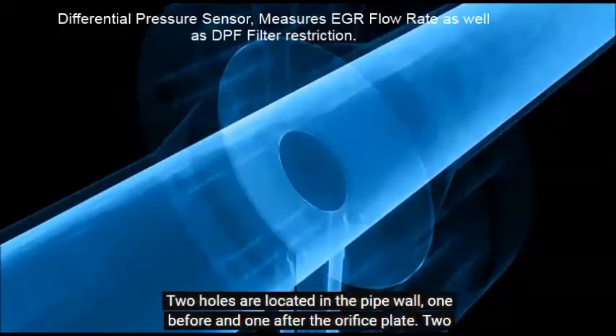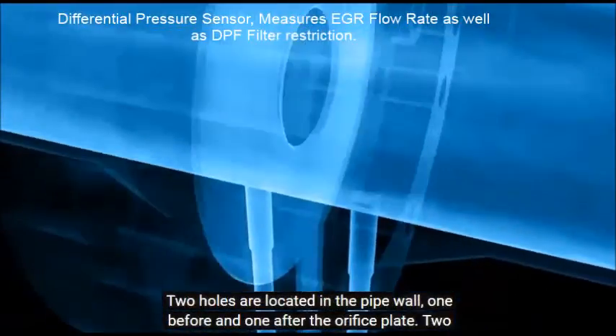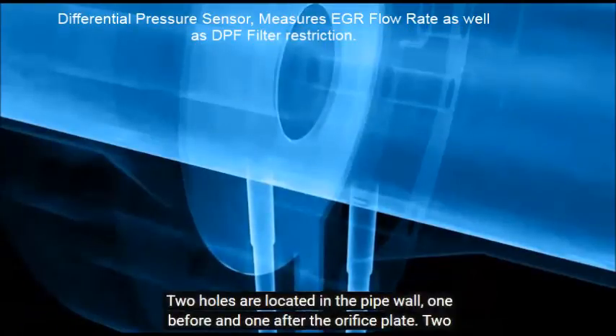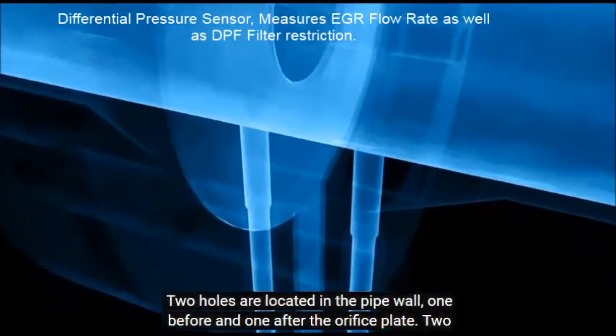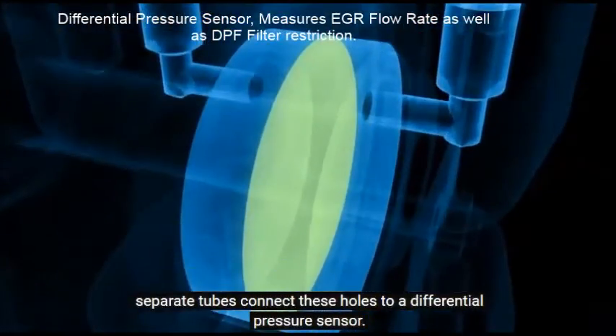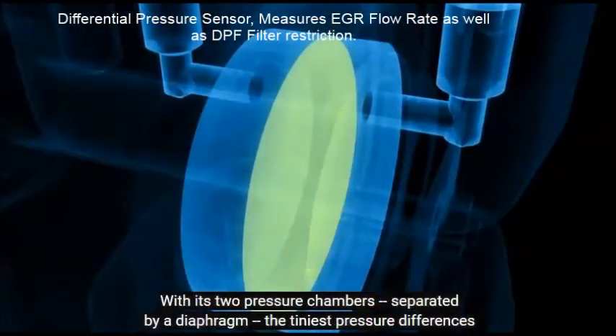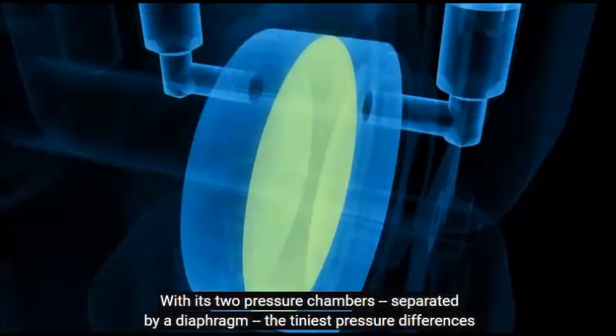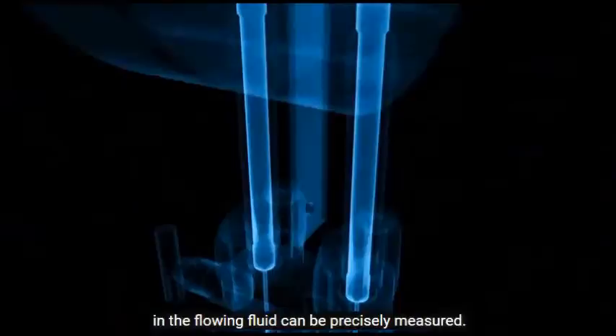Two holes are located in the pipe wall, one before and one after the orifice plate. Two separate tubes connect these holes to a differential pressure sensor with its two pressure chambers separated by a diaphragm. The tiniest pressure differences in the flowing fluid can be precisely measured.